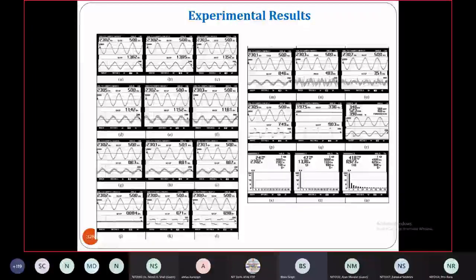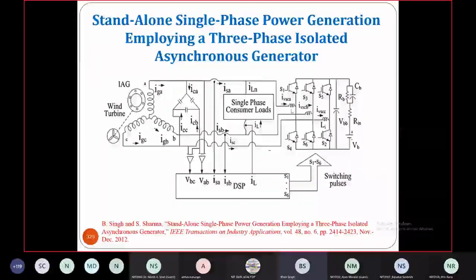You can see the fourth leg inverter neutral current. It takes care of that. One phase load is not there, so the neutral current is also there, and even then the neutral current was there because three square waves are added, so you will have a current like this. So it works very well without any problem. Your voltage THD is only 2.4%, because it's a standalone system, and the current THD of the generator is 4.7%, whereas the load current THD is 41.8% of this load. It's a single phase load.